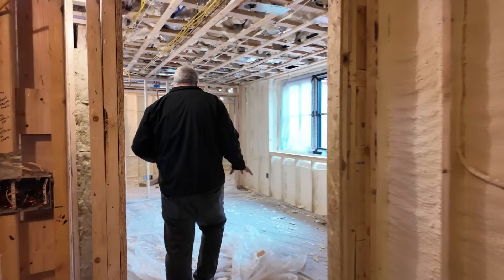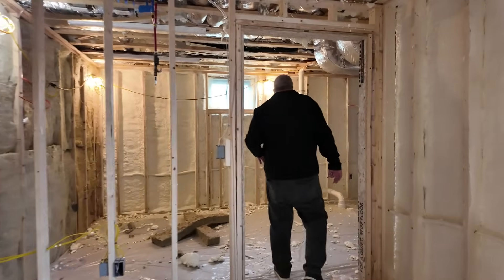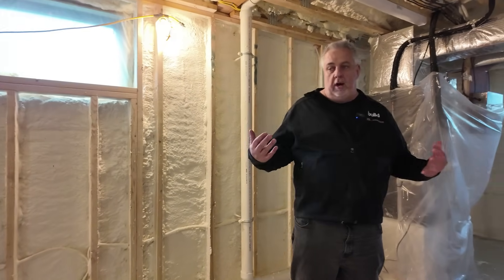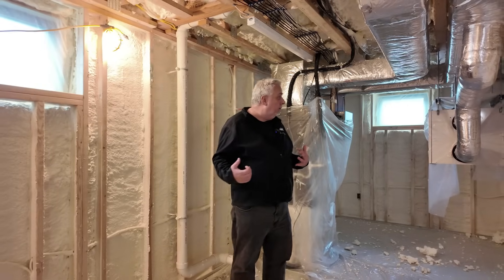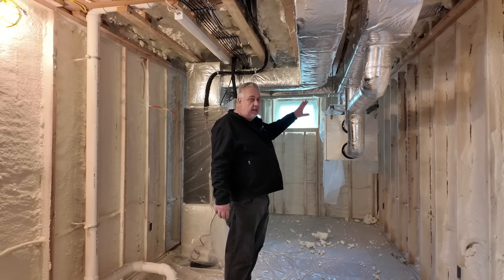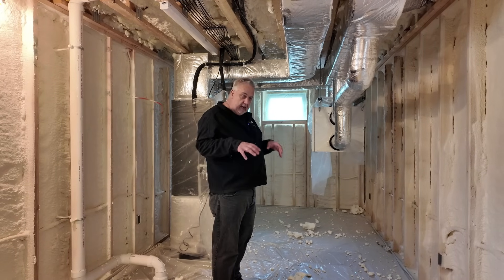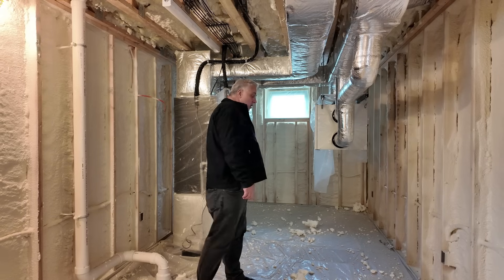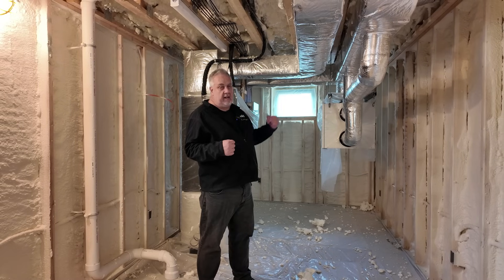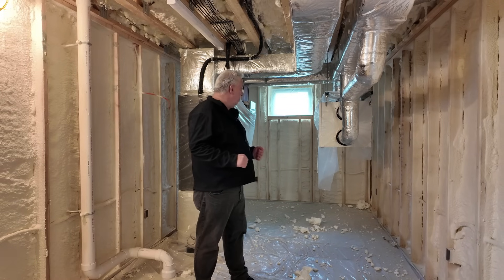They've been insulating for acoustical and thermal purposes, and you can see they did a bunch of overhead work too. We're in one of the utility spaces here. You can see our RenewAire ERV — that's pumping in outdoor air that gets filtered. It's an energy recovery ventilator, so we don't pay the penalty for the heated air we've purchased via the Mitsubishi system. It strips the heat off and puts it on the incoming air so it enters the house as heated air from energy we already paid for.